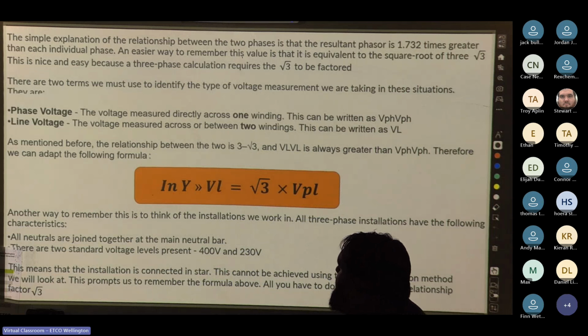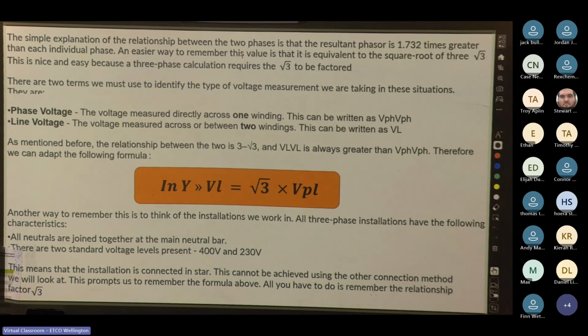So a simple explanation: between two phases there is a resultant phasor that's 1.732 times greater than each individual phase. The easy way to remember this value is square root of 3, because three-phase calculation requires square root of 3 to be factored. So two terms we must identify. Phase voltage, measured directly across one winding, is written as VPH, and line voltage, measured across or between two windings, can be written as VL. The relationship is square root of 3, and VL is always greater than V phase.